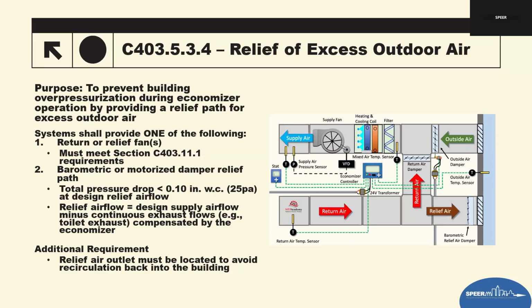So when an economizer opens, outdoor air coming in increases dramatically. So if the building doesn't have a proper relief strategy, it becomes overpressurized, leading to doors blowing open or difficult to close, infiltration through the building's envelope, which is energy waste, poor comfort, drafts, pressure imbalances, and then reduced system performance. So the code requires a defined relief method to avoid all of those.